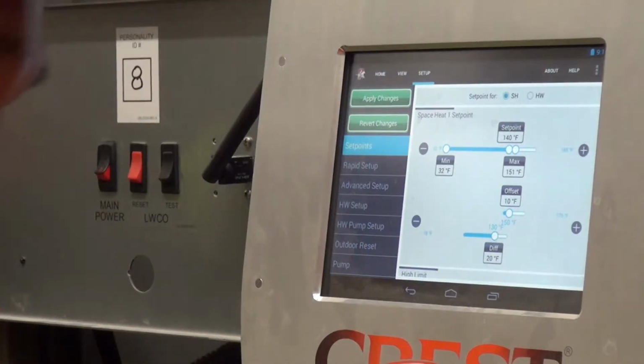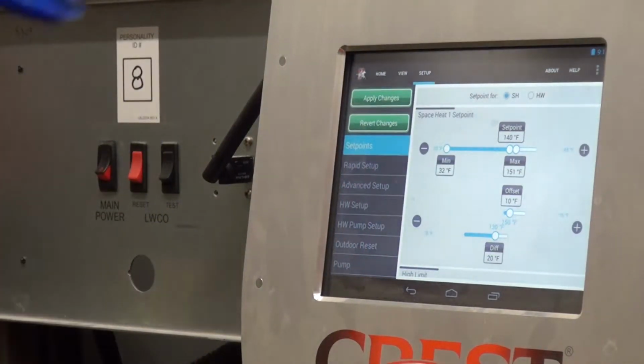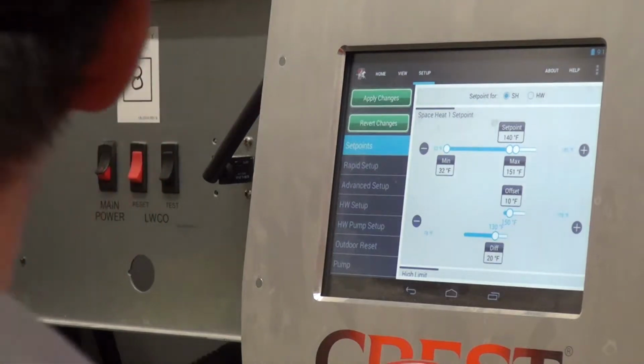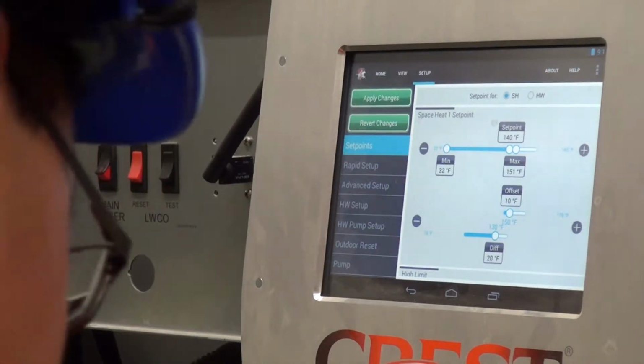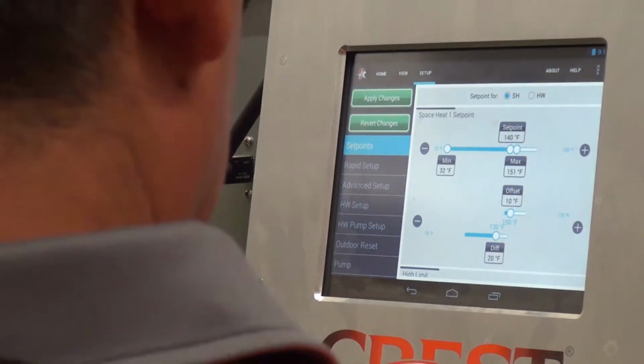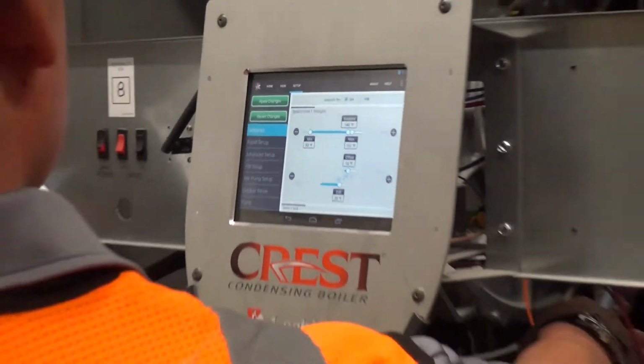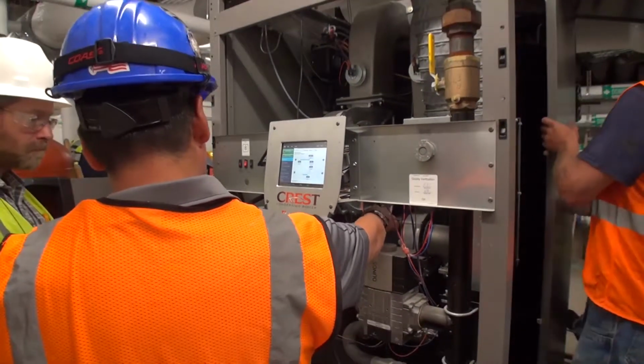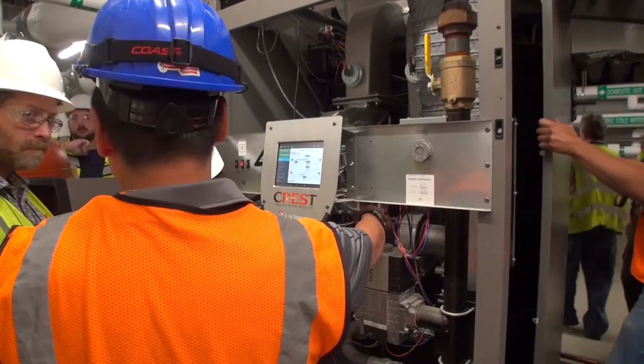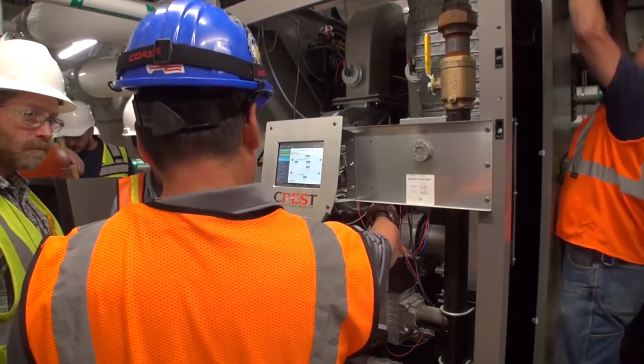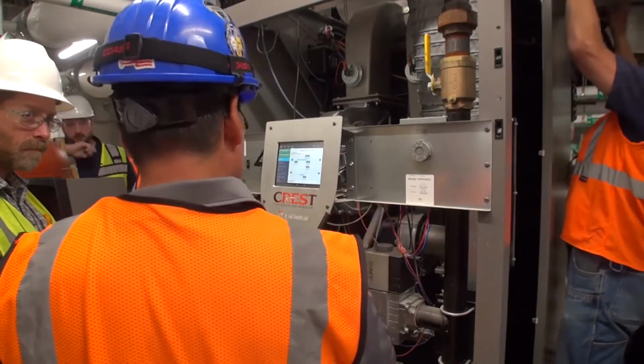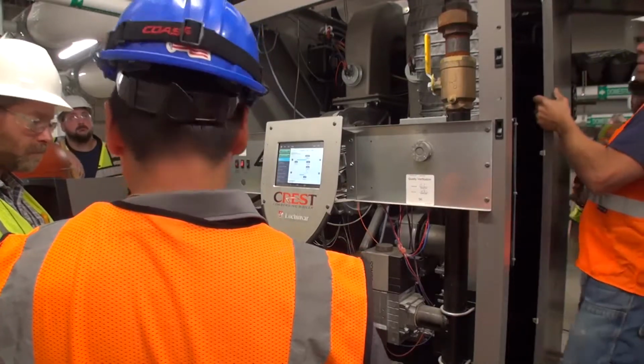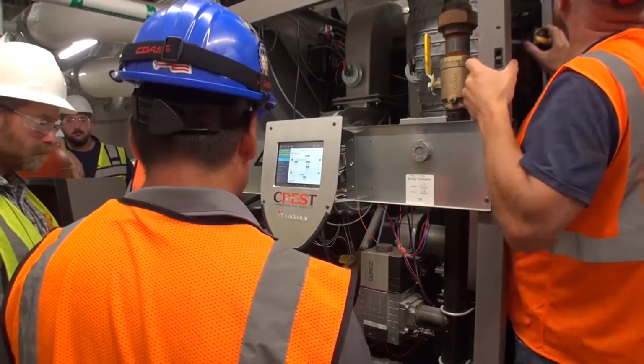We pass this back to you one more time. So these use what they call a negative regulation design. This valve is measuring this air pressure. So what happens is the controller controls the speed of the fan. As the fan speeds up, it draws a higher negative pressure, and this valve opens more and more. So that's how it controls the throttling of the valve.